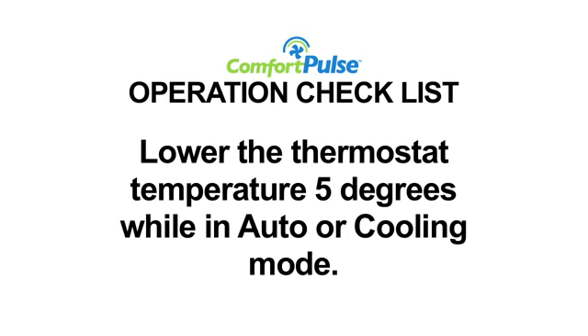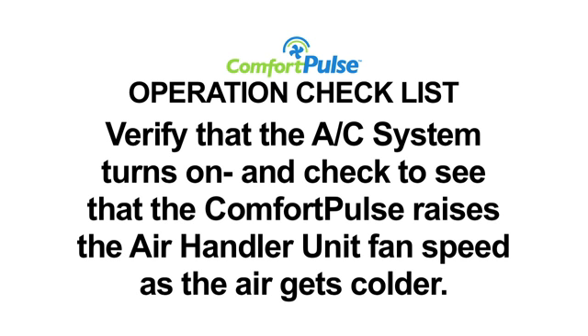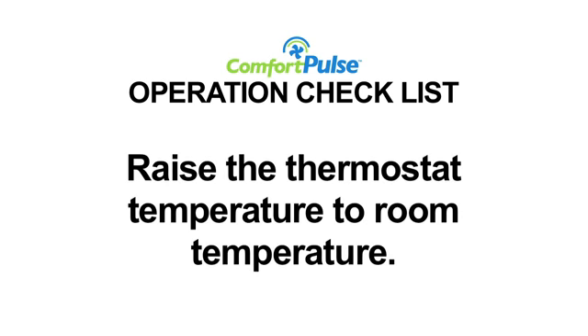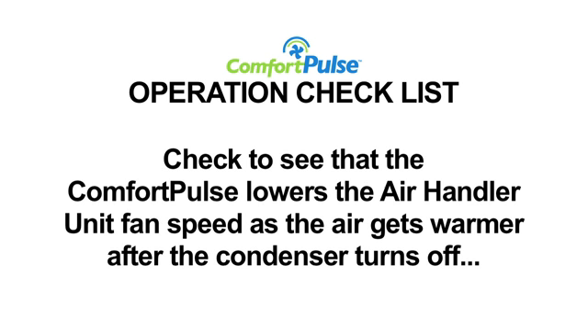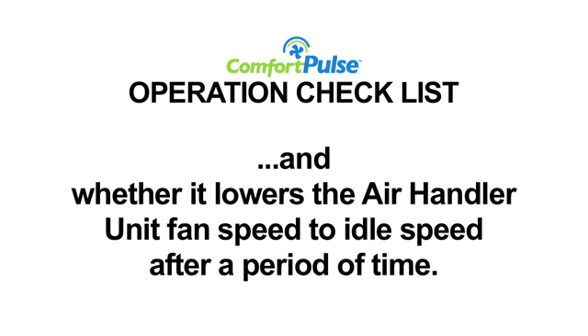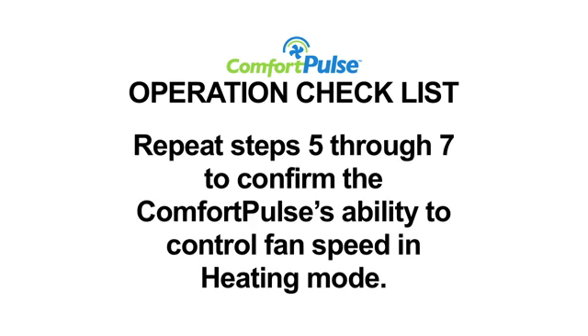Lower the thermostat temperature 5 degrees while in auto or cooling mode. Verify the AC system turns on, and check to see that the Comfort Pulse raises the air handler unit fan speed as the air gets colder. Raise the thermostat temperature to room temperature. Check to see that the Comfort Pulse lowers the air handler unit fan speed as the air gets warmer after the condenser turns off, and whether it lowers the air handler unit fan speed to idle speed after a period of time. Repeat steps 5 through 7 to confirm the Comfort Pulse's ability to control fan speed in heating mode.